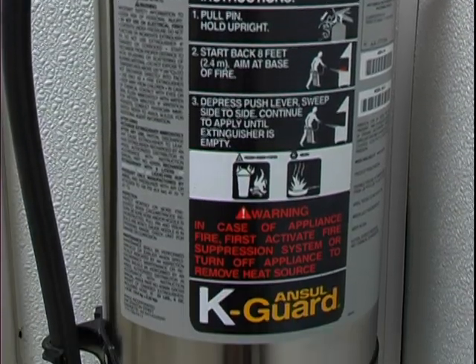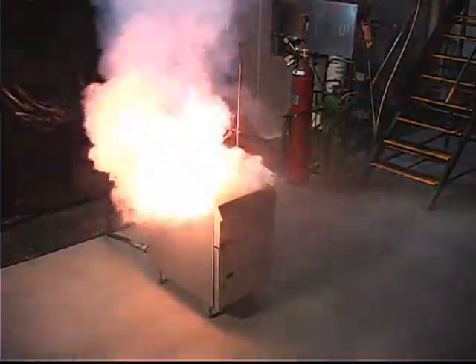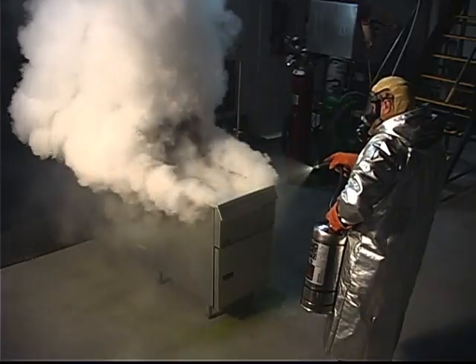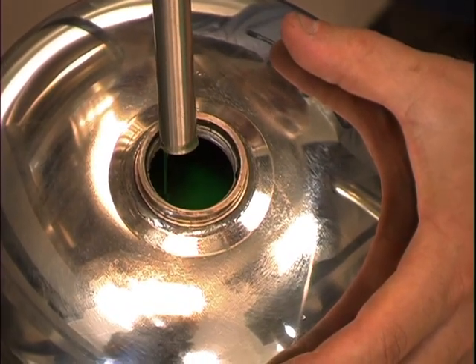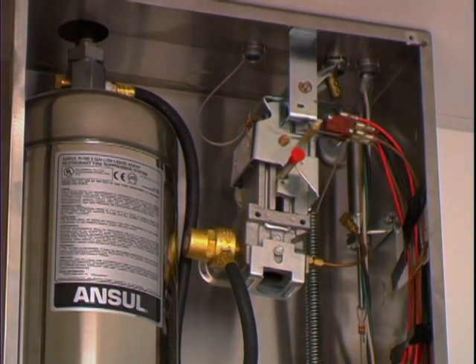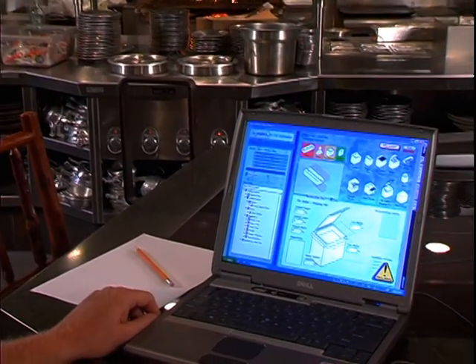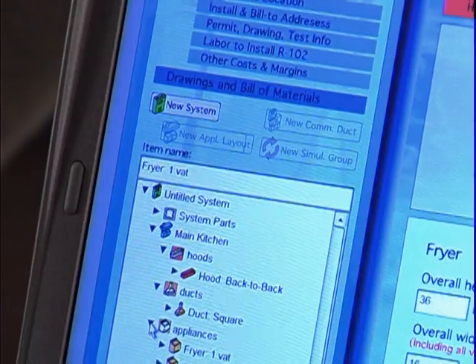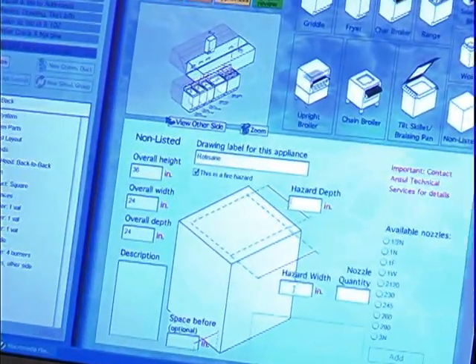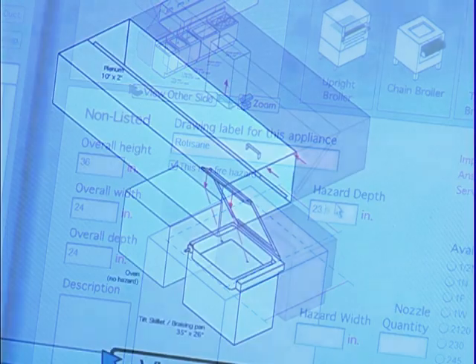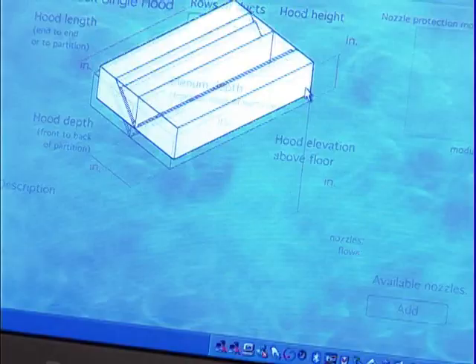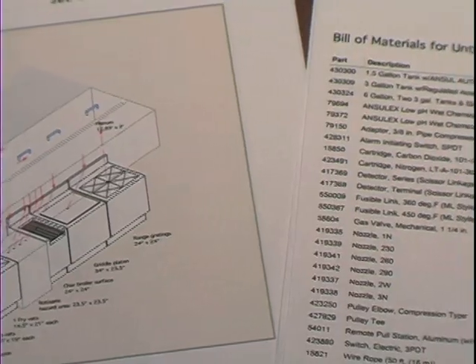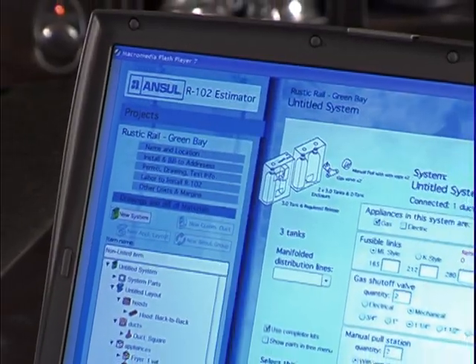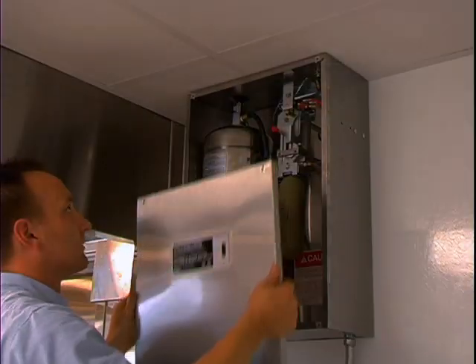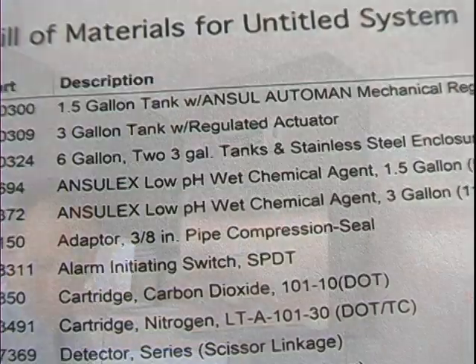Giving your R102 system added protection is the ANSUL K-Guard Kitchen Fire Extinguisher. Meeting tough UL, ULC, NFPA, and other pertinent international standards, the K-Guard Extinguisher uses ANSULEX, the same reliable extinguishing agent in your R102 system. To ensure the best possible protection for your kitchen, our distributors use the R102 Estimator. This revolutionary computer program is used to design the R102 restaurant fire suppression system best suited for your application. Whether your kitchen has one hood or multiple hoods, the R102 Estimator uniformly designs the appropriate system, generating the drawings and bill of materials needed for installation. The R102 Estimator assures ANSUL distributors proper design and installation, and keeps the fire suppression system up to date with the latest UL requirements.